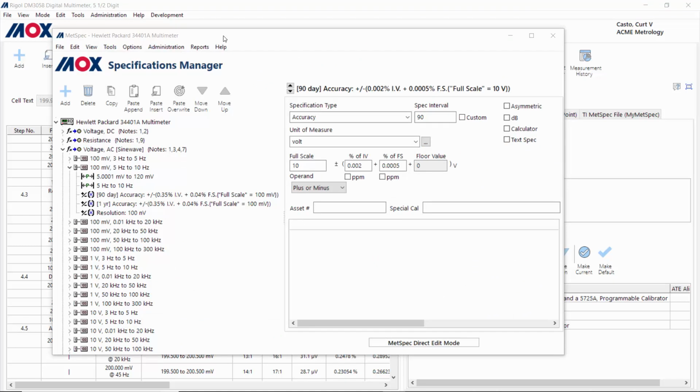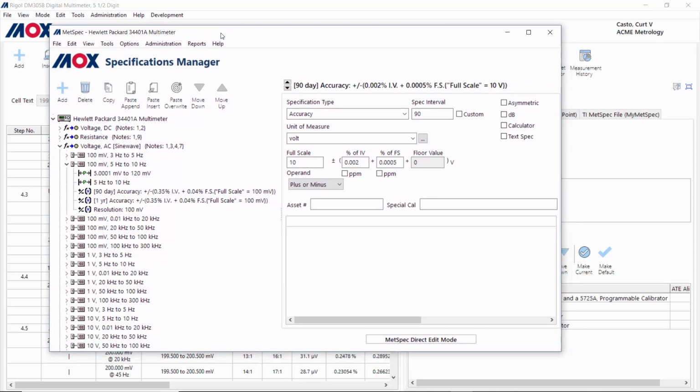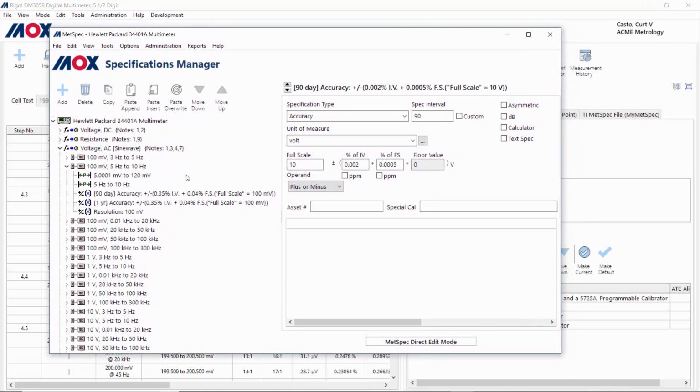One of the primary uses for these Metspec instruments is as calibration standards in MPS, and that's what they're used for the most. However, if you have a Metspec instrument, you can also use it to build the datasheet for it in MPS. In the test point builder, there's a button where I can choose a Metspec range and have it load the test point builder to actually create test points using the Metspec instrument's specifications.